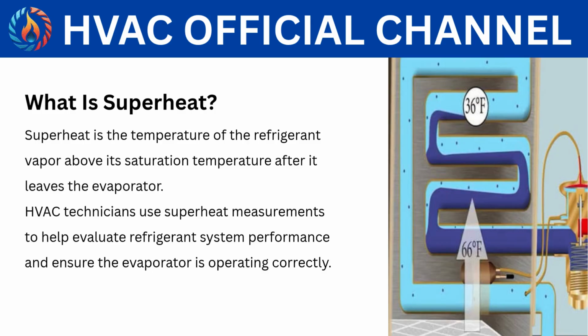What is superheat? Superheat is the temperature of the refrigerant vapor above its saturation temperature after it leaves the evaporator. HVAC technicians use superheat measurements to help evaluate refrigerant system performance and ensure the evaporator is operating correctly.